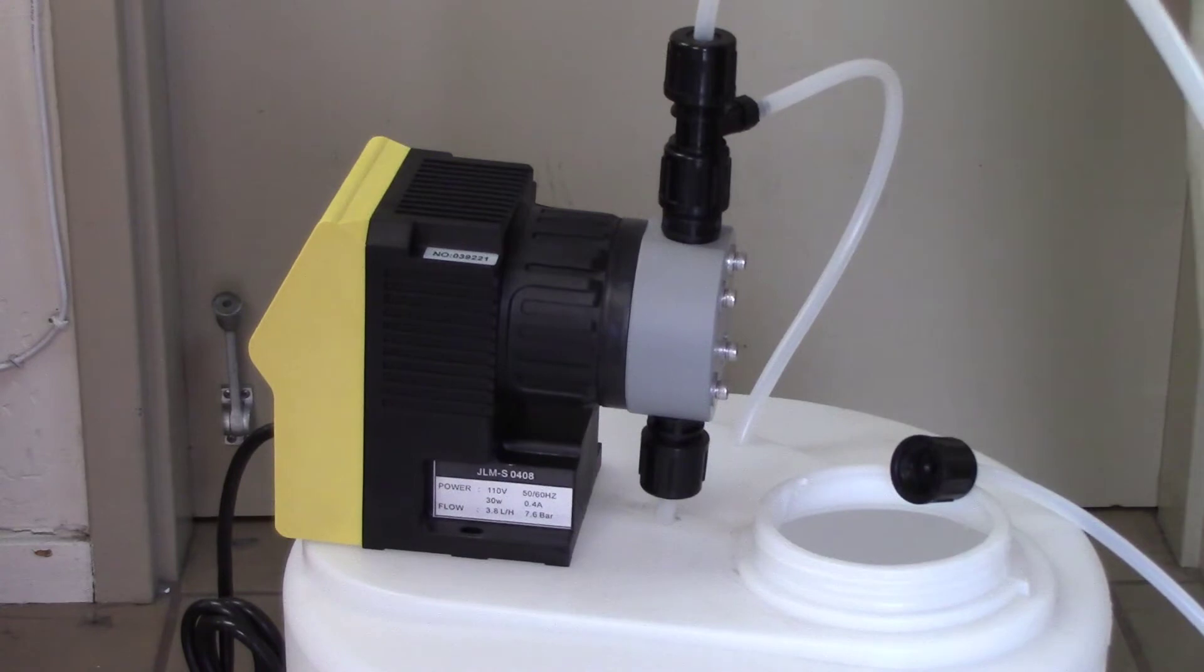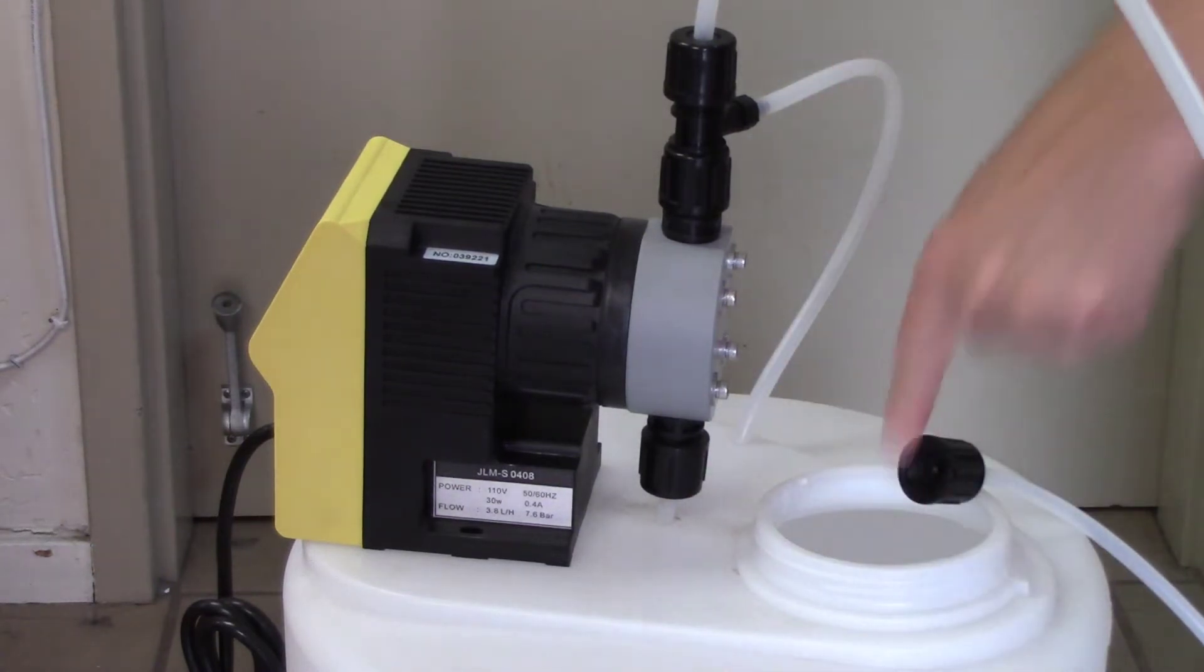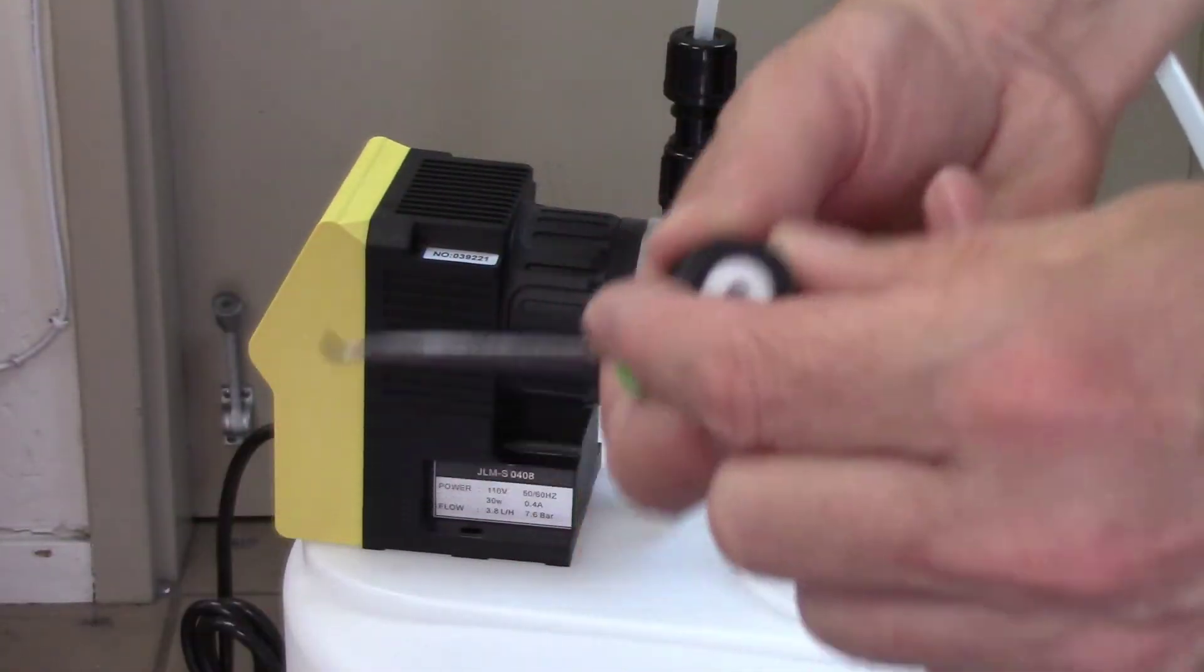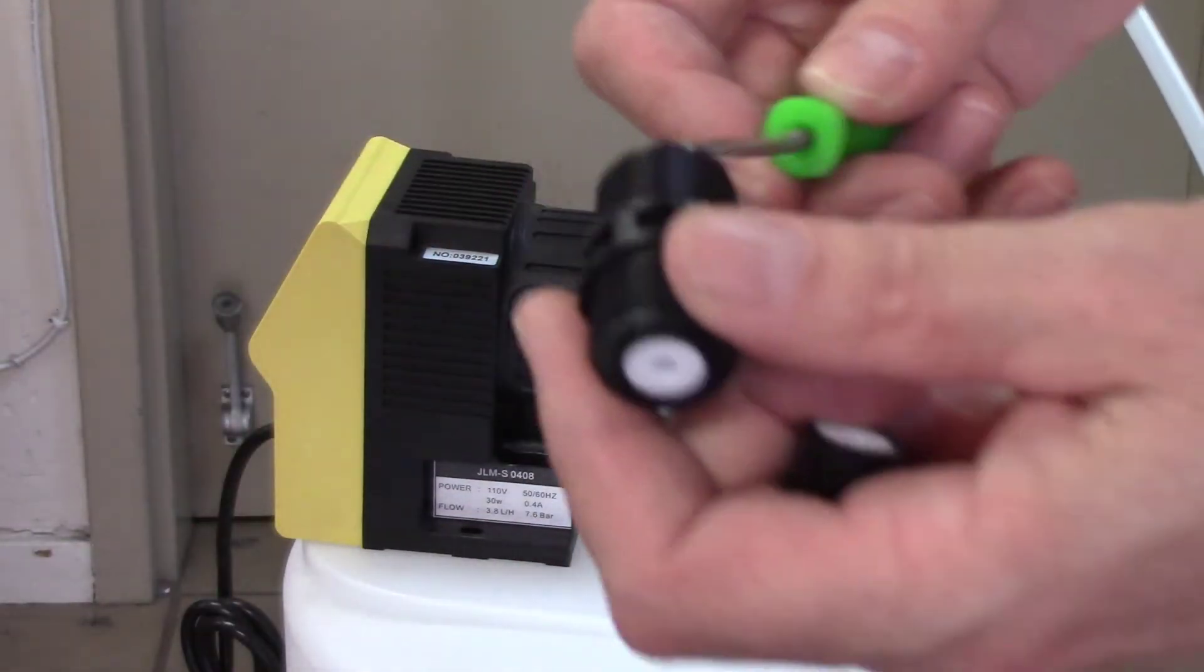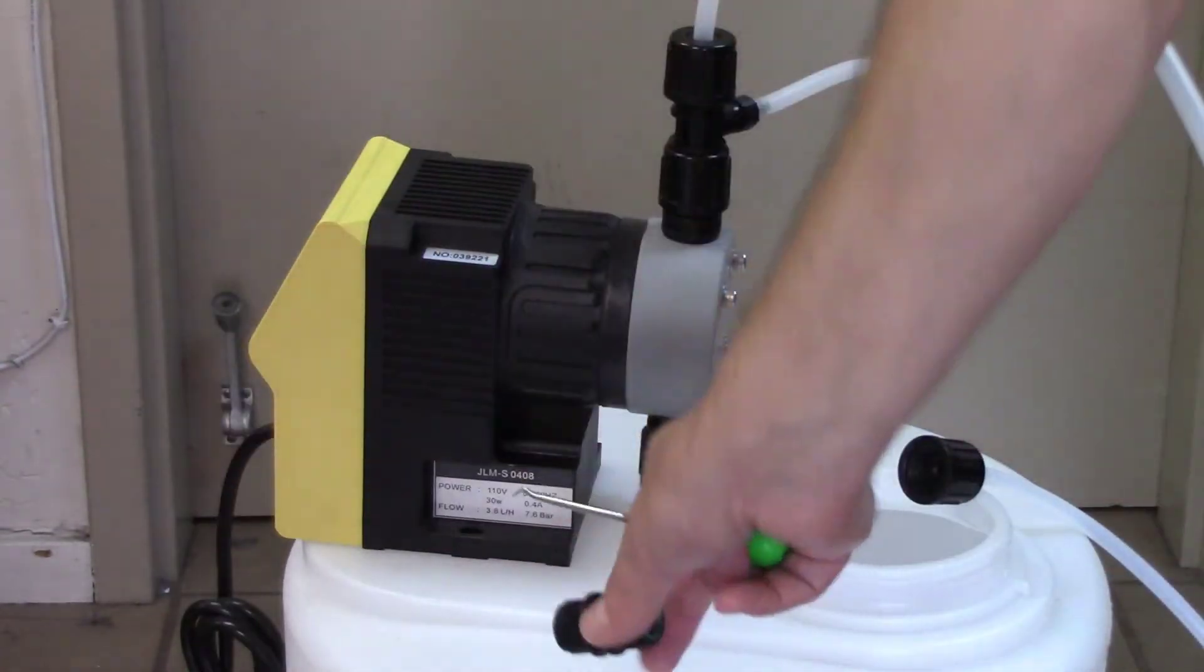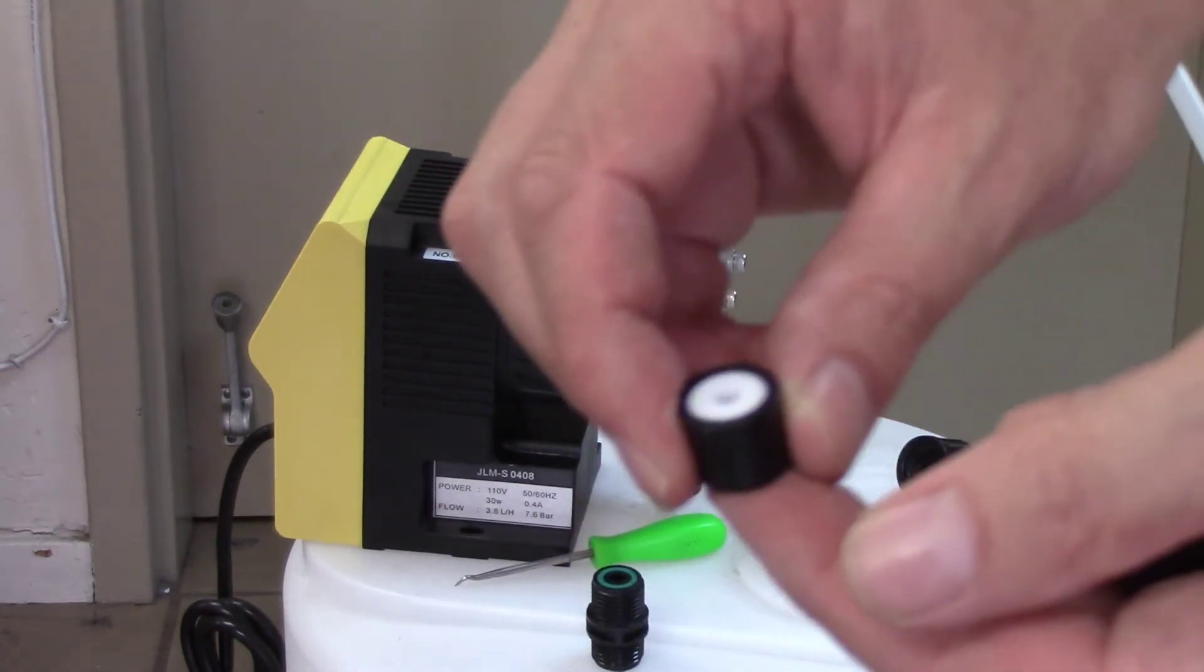The other style is the same on all the inlet/outlet fittings. This is the outlet going to service, the inlet coming in from the pump, and then the foot valve in the bottom. All of those have the same type. When you unscrew them, I've got one in my hand and I've got one that's sitting in there that I've already pushed forward. You need something to go through this end and push it out, so then you're holding both of them in your hand. After you get them cleaned off and dried off, you can blow through them one direction and you can't blow through them the other direction, and that's how they work.